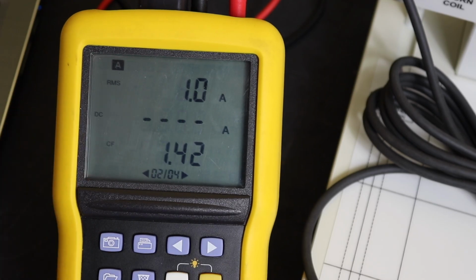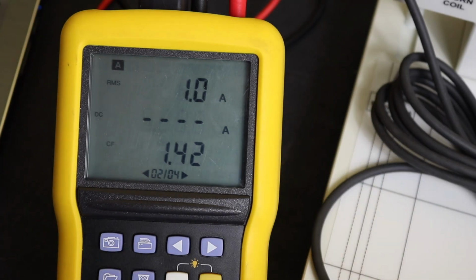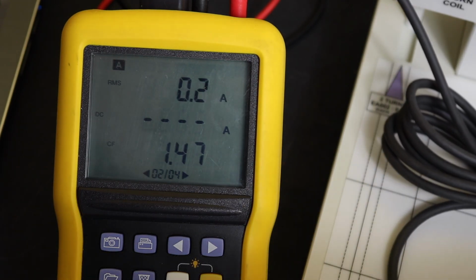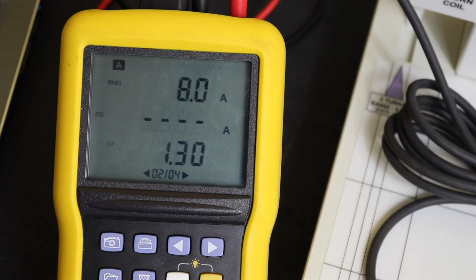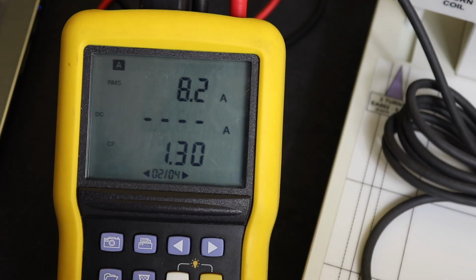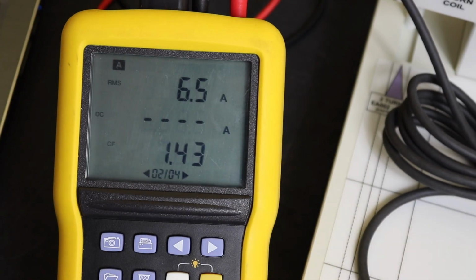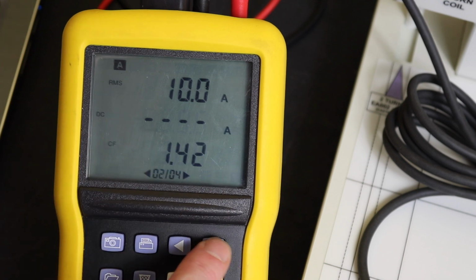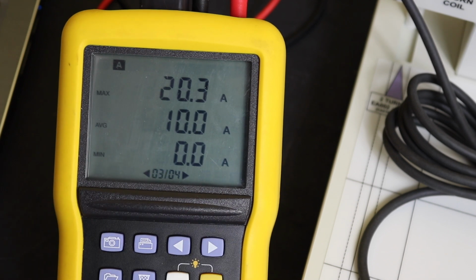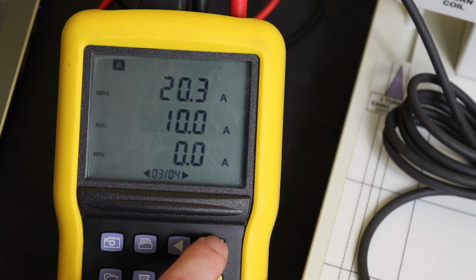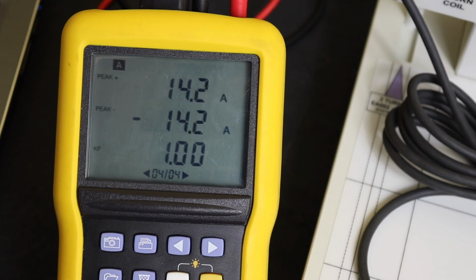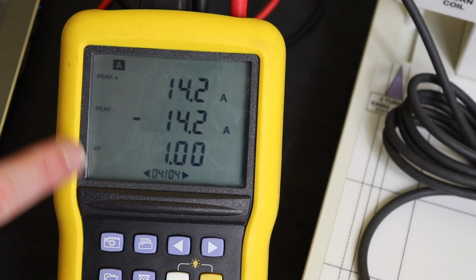We've got 1 amp, and what I'll just do is put the clamp onto the 10-turn coil. And we're out of range because we're on the 5 amp range. So we'll set that to 100, and we get 10.0 amps, crest factor 1.42, all good. Maximum is 20.3 amps, 10 amps, that must be, so over range function it went. Minimum is 0. And then we get the peak values there, and we've got this KF value.